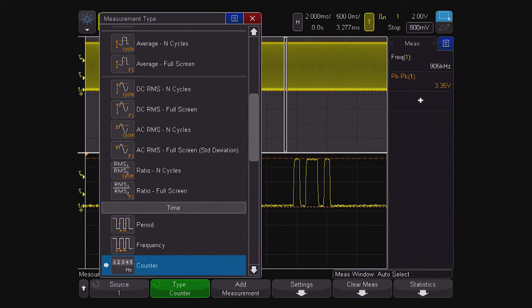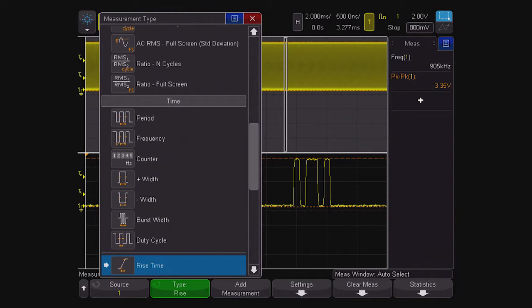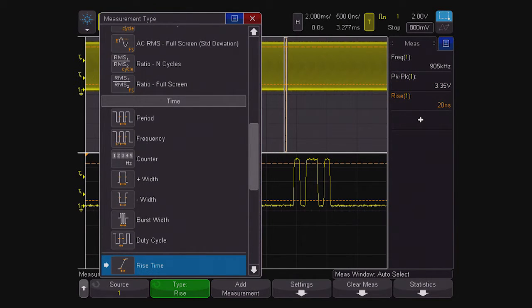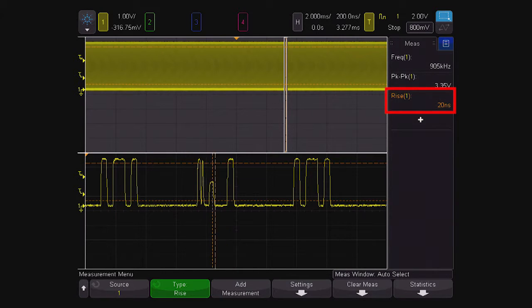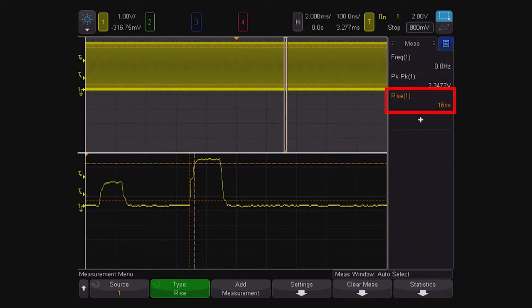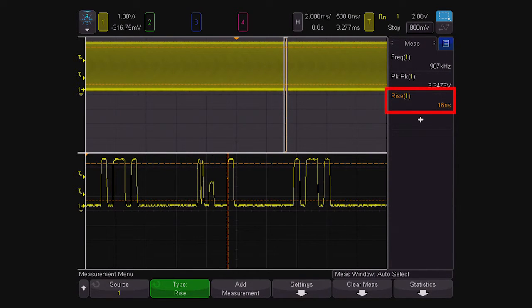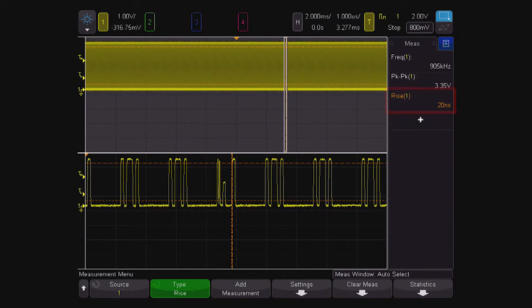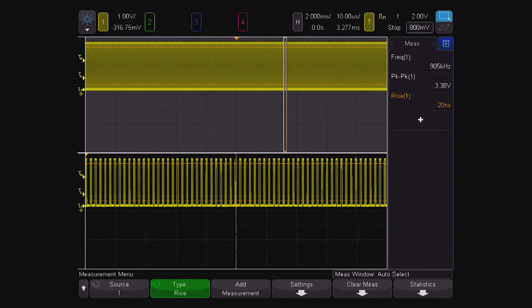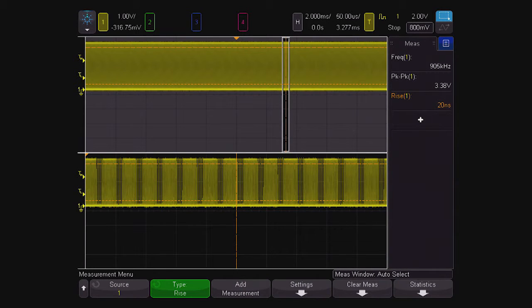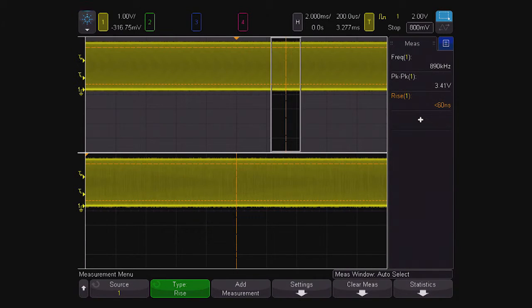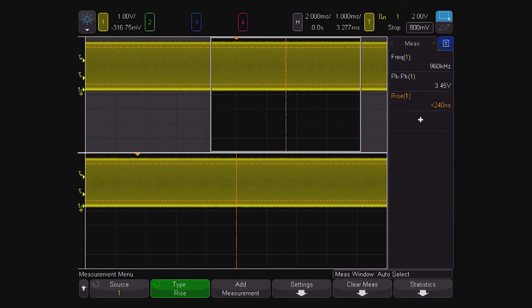For analysis tasks, the Agilent scope also has the ability to measure rise times. The rise time measurement is showing about 20 ns, but if we zoom in further, we see that the measurement changes to about 16 ns. The measurement is not consistent as we zoom in and out, and we don't see the same measurement precision as the Tektronix instrument. Agilent's user guide indicates that automatic measurements only use the displayed data points on the screen, so as we zoom in or out, measurements have different data available. That seems like a limitation to making consistent, accurate measurements.